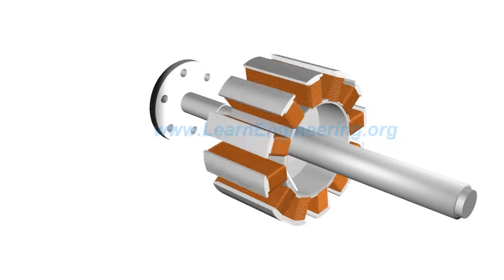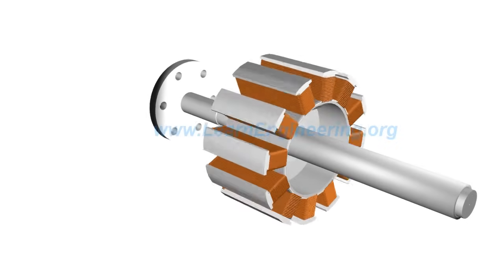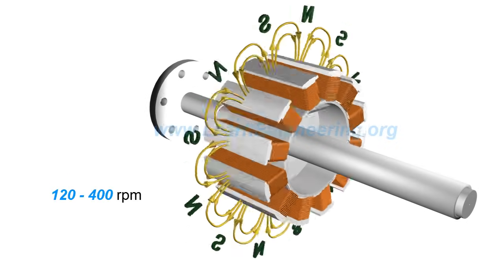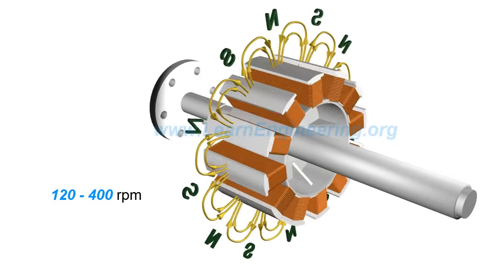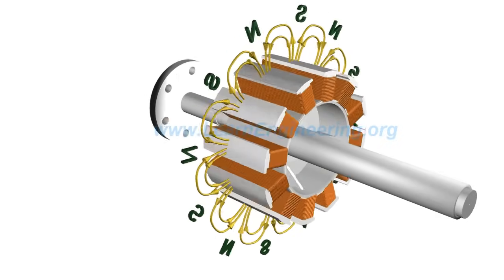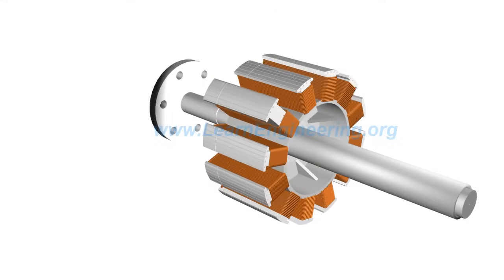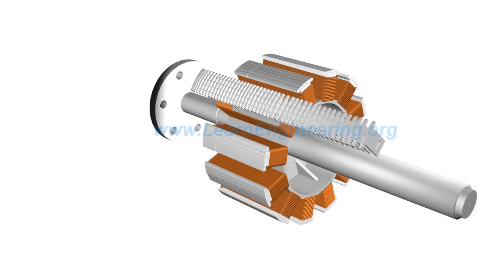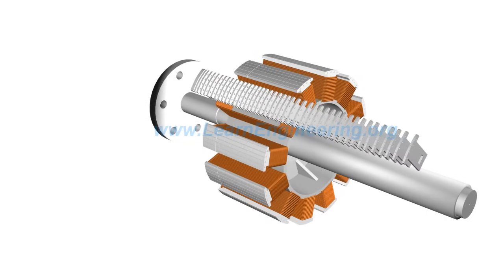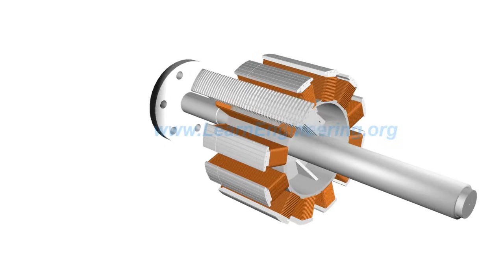Salient pole rotors are used when the prime mover rotates at a relatively lower RPM. The pole core is used to effectively transfer magnetic flux, and they are made with fairly thick steel lamina. Such insulated lamina reduces energy loss due to eddy current formation.